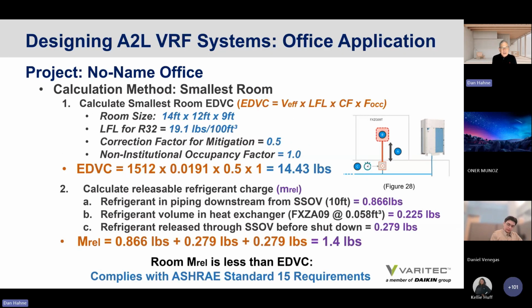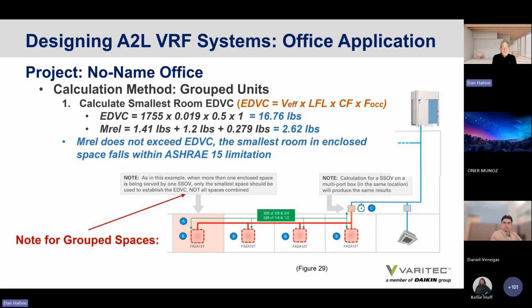Using a safety shutoff valve, we can now determine that the overall effective dispersal volume charge is calculated at 14.4. However, the releasable refrigerant charge of this specific example is 1.4 pounds, so it meets and conforms to the actual intent of standard 15.